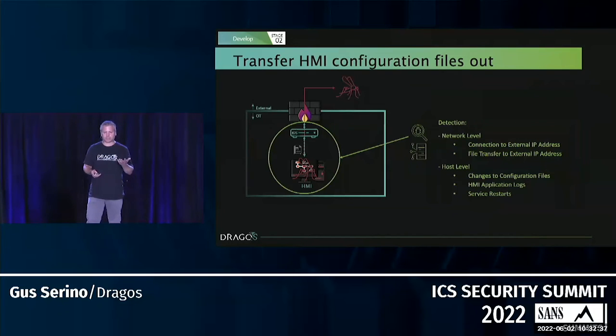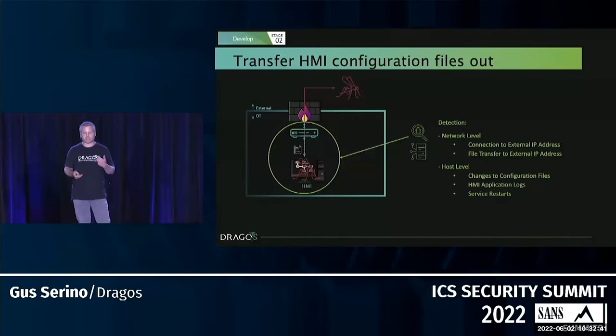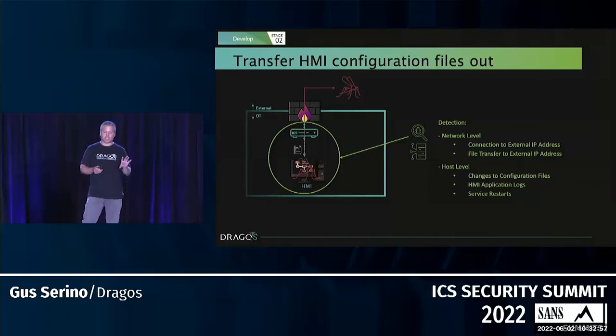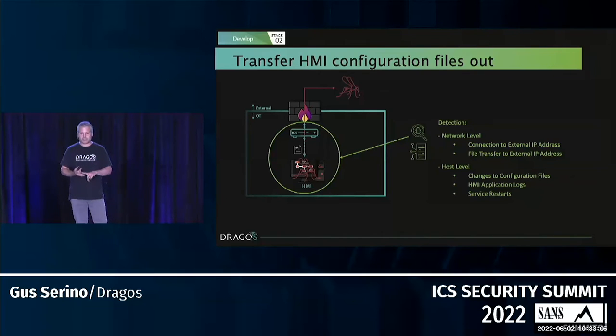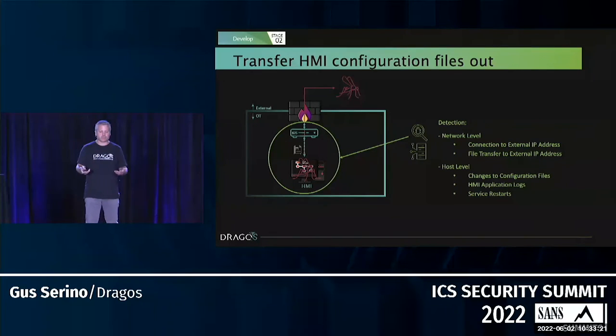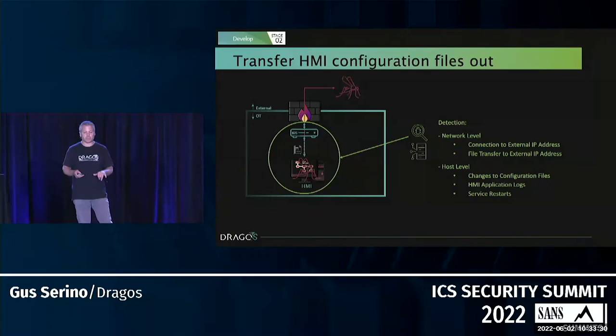For detection during the exfiltration phase: look for connections and file transfers to external IP addresses, check whether that's normal for your HMI, and look for changes in configuration files. HMI application logs are a really good source of information to include in your collection management framework — they record user logins, set point changes, configuration changes, and more. Also watch for service restarts: when configurations change, you often need to restart the service, and an unexpected restart may indicate something is up.